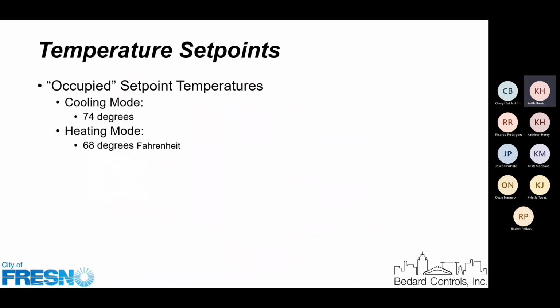Like I mentioned before, the set points that have been described for this project, that are being programmed into the thermostat and into the system, is a set point in cooling mode, meaning air conditioning, down to 74 degrees. Now you can be anything above 74 degrees that you would like, but you can't currently go below 74 degrees, and I'll talk about that more in just a minute. In heating, right now it's 68 degrees or anything less than 68 degrees.